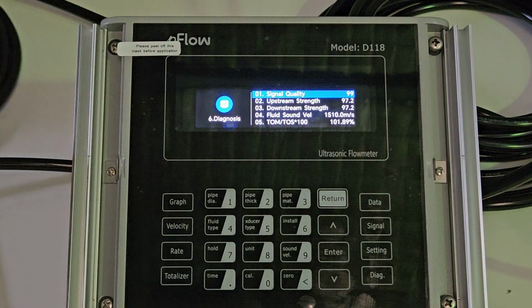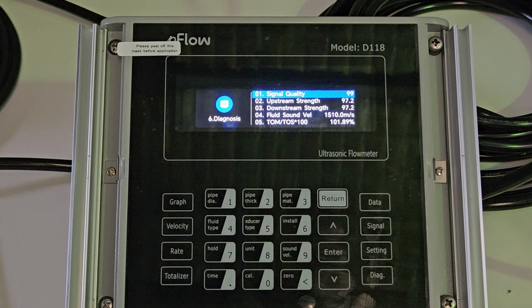Then further down there is TOS. This value shown is the transit time ratio. A normal expected ratio is 100% with 3% allowed variance. So between 97 and 103%. If any of these checks are out of range, it can indicate a problem with the application or installation. Please recheck parameters and installation, or check through the installation guide and manual to troubleshoot. Maybe there is a parameter incorrectly set or a problem like not enough straight pipe length causing flow turbulence, aeration, or too much suspended solids.